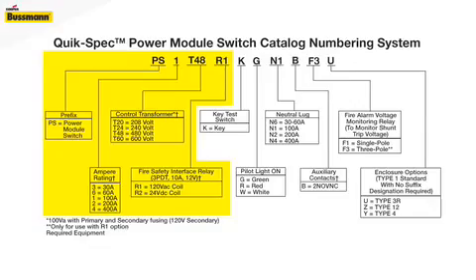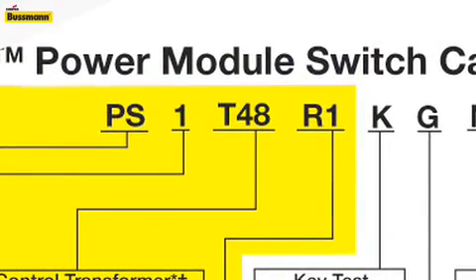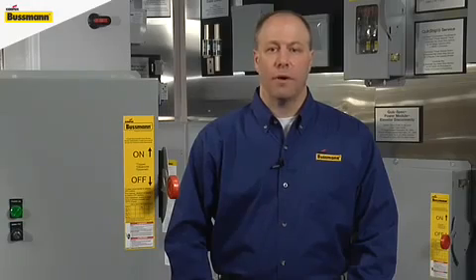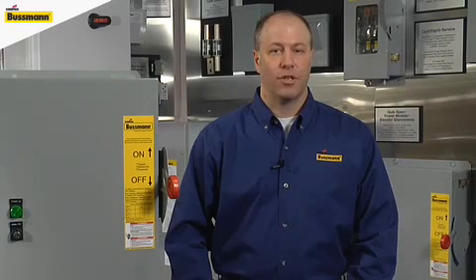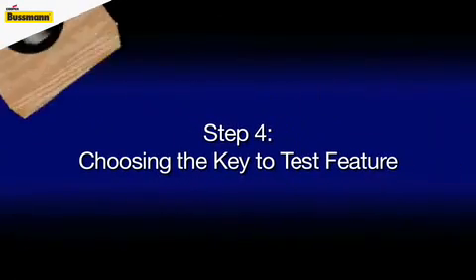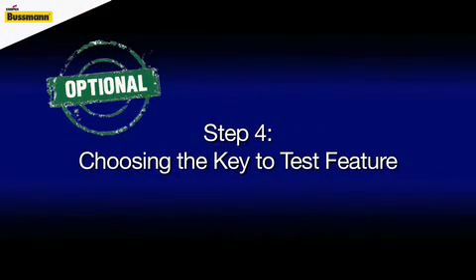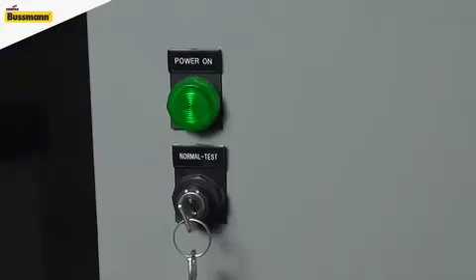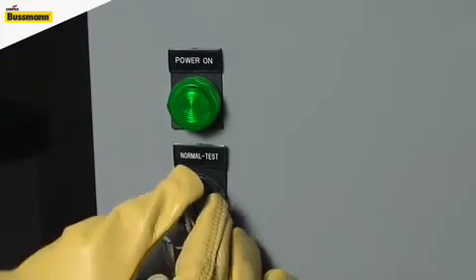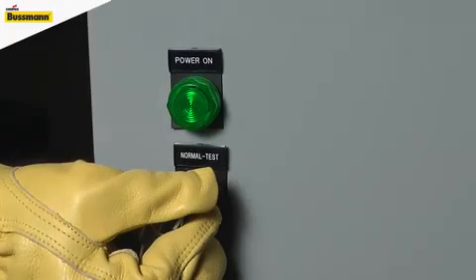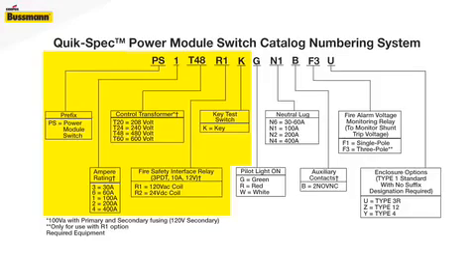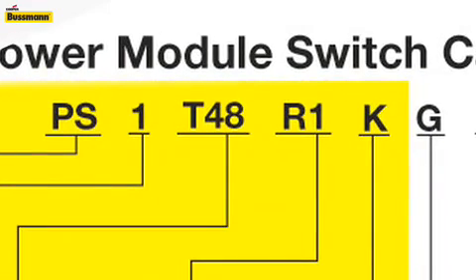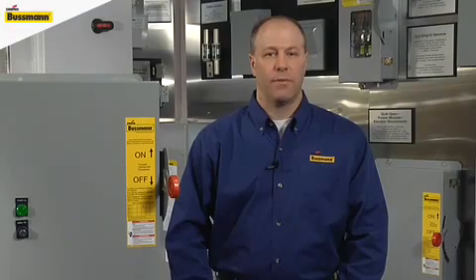So far we have selected three different sections of the power module part number. One very convenient feature is the ability for the mechanic or inspector to check operation of the shunt trip device on site at the panel location. The key-to-test feature in step four allows an easy and safe way to test for proper operation. If you do not select this option, the only way to test the system is to send a signal from the fire alarm control panel. Simply add the K code into the part number configuration as shown. If you do not want this or any other optional feature, simply eliminate the space in the part number sequence and your final part number will be shorter.